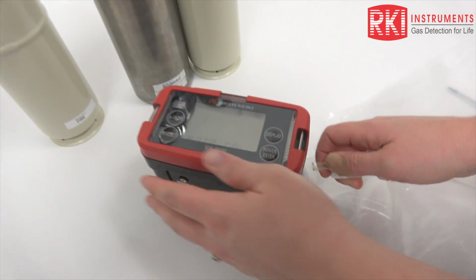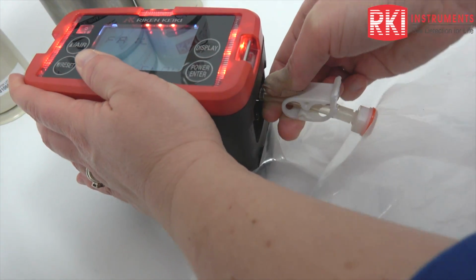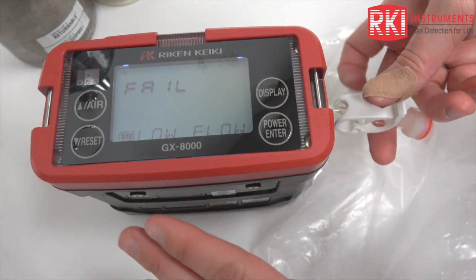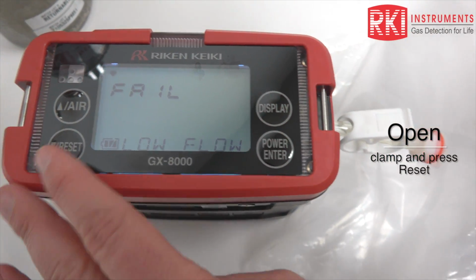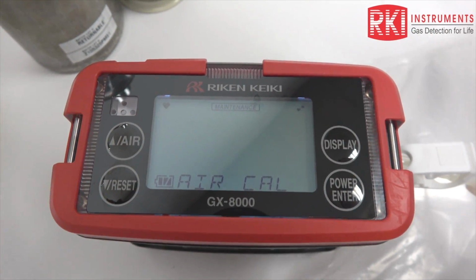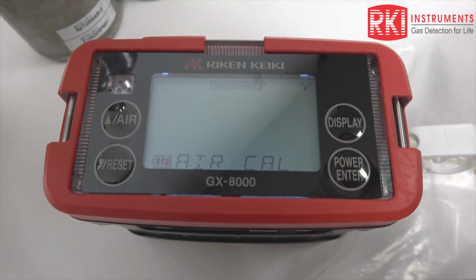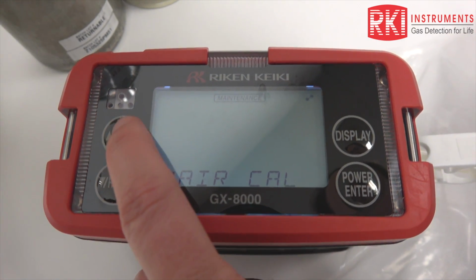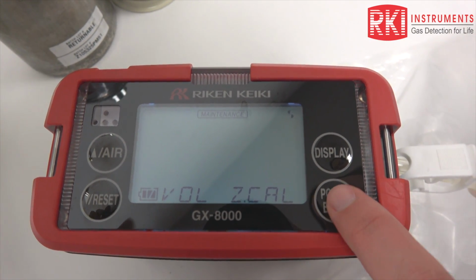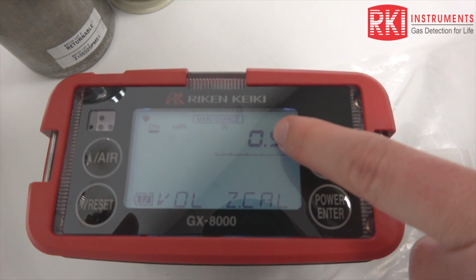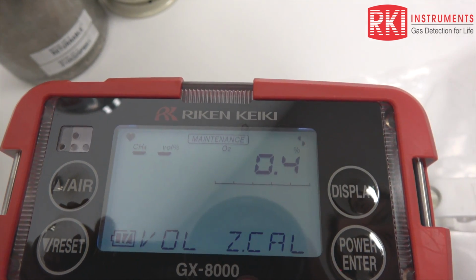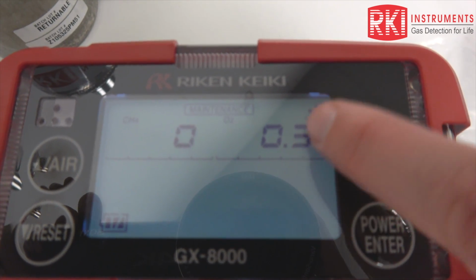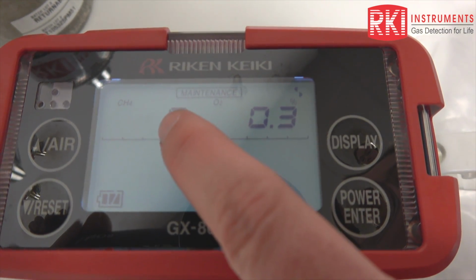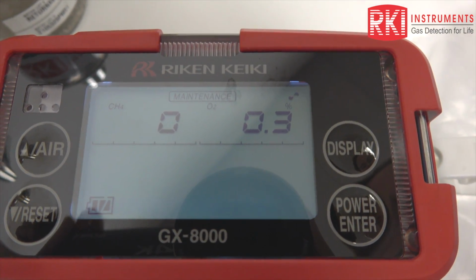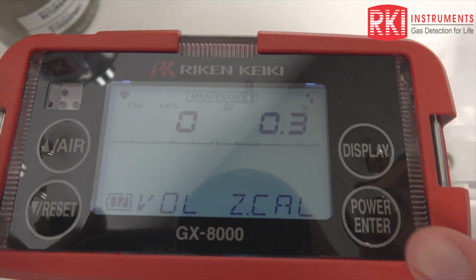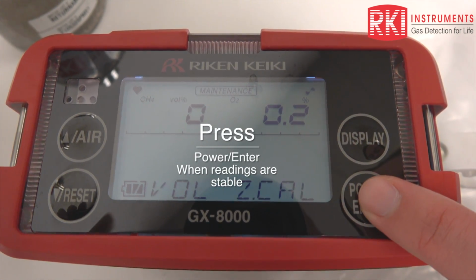I'm going to hook it up to my GX8000 again. You can hear it going into low flow again. I'm going to open the clamp on the bag and then press reset. So now my GX8000 is drawing nitrogen from my gas bag. So I'm going to go to my Vol Z Cal, power enter. This is the oxygen reading and this is the methane reading. So you can see oxygen is almost down to 0 and the methane came up and it's to 0. Both of these readings seem stable. So I'm going to go ahead and push power enter.